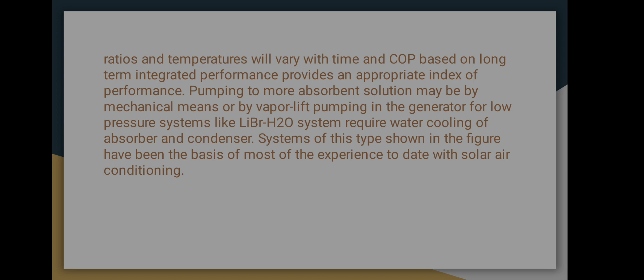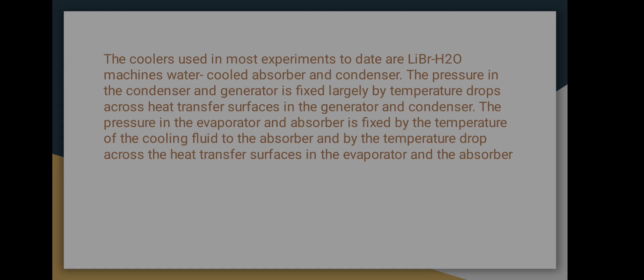The coolers used in most experiments to date are lithium bromide water machines, with water cooled absorber and condenser. The pressure in the condenser and generator is fixed largely by temperature drops across heat transfer surface in the generator and condenser. The pressure in the evaporator and absorber is fixed by the temperature of the cooling fluid to the absorber and by the temperature drop across the heat transfer surface in the evaporator and the absorber.